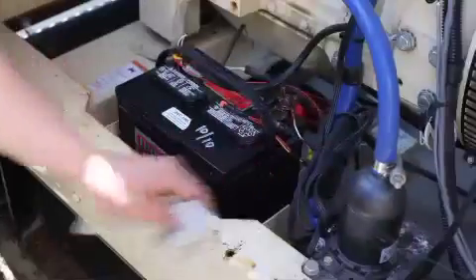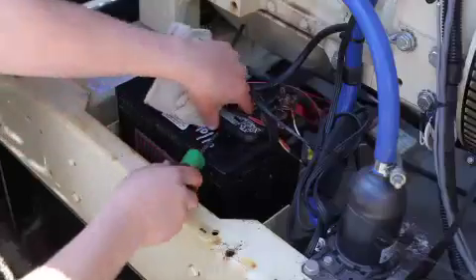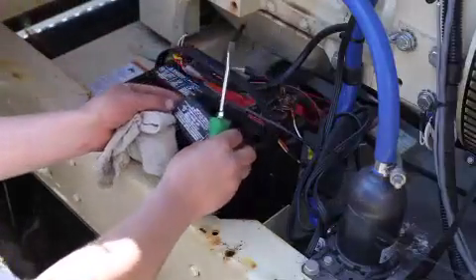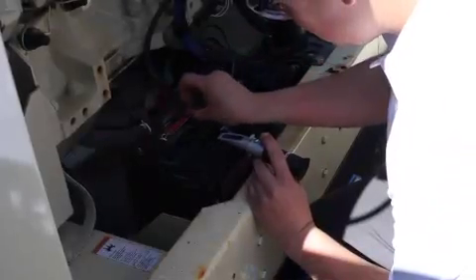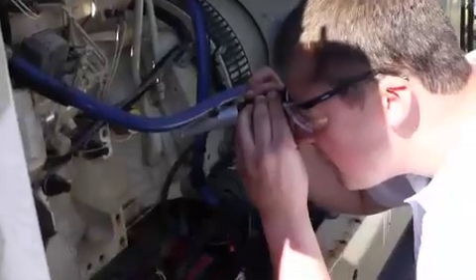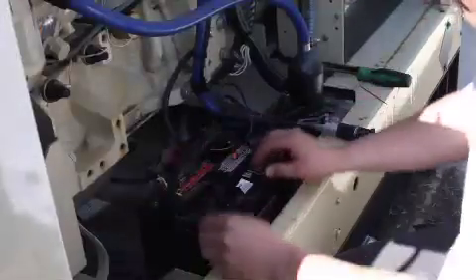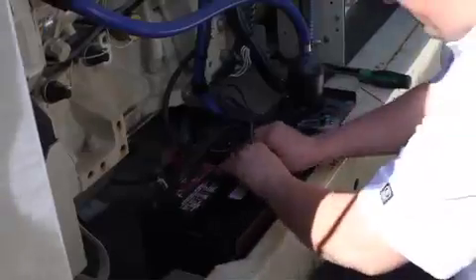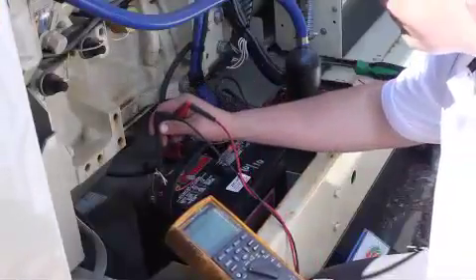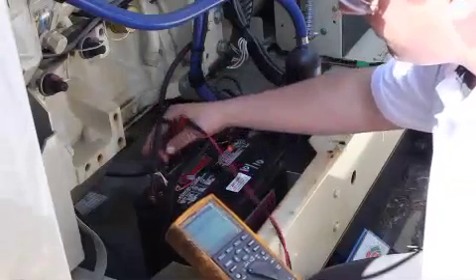A typical planned maintenance contract visit will carry out battery maintenance service and checks, including: check all battery and starter connections, remove cell caps and check electrolyte levels, take electrolyte samples and examine with a visual test device, replace caps after checking, examine battery cleanliness, and connect an electronic tester to verify battery cell voltage stationary and during run-up.